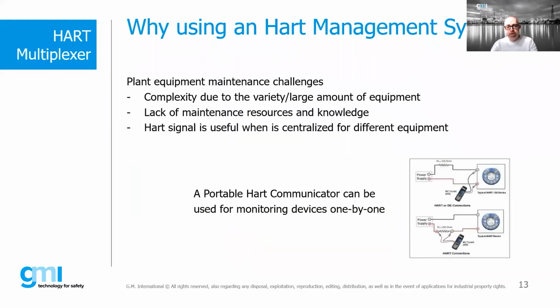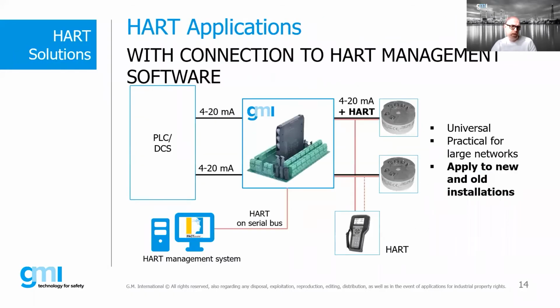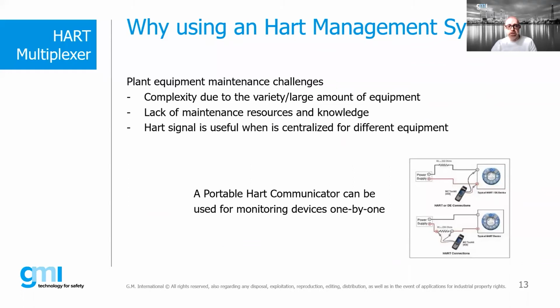In order to integrate the measurements provided by our device into a control system, it's possible to implement a point-to-point connection of the 4-20 milliamp signals, or a connection via remote I/O modules or HART multiplexer. The HART protocol represents an intermediate step in the transmission from analog to digital communication. The HART multiplexer is the best solution for gathering all HART data into a single point software.